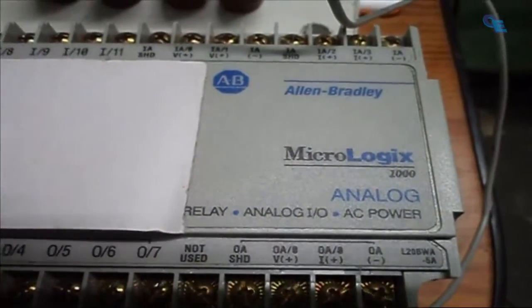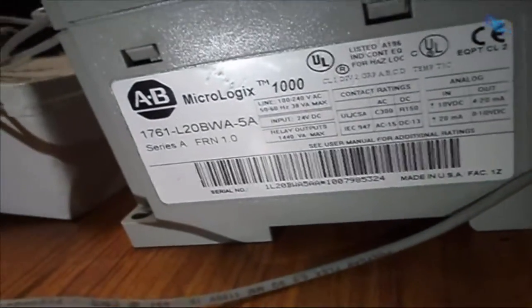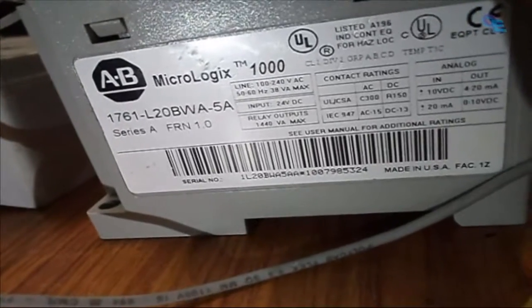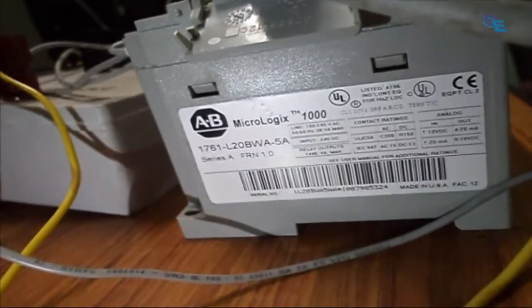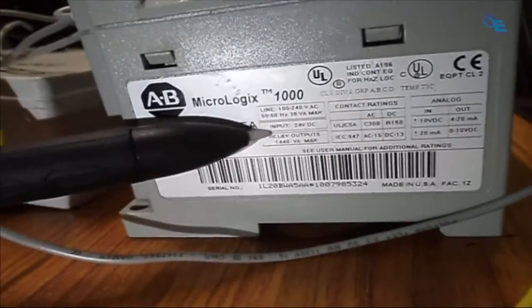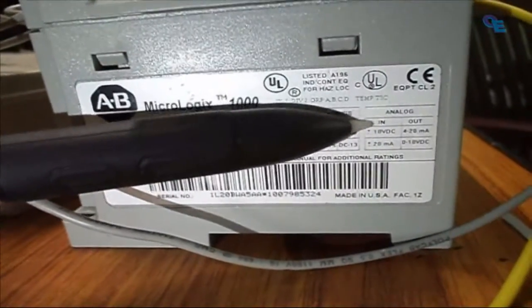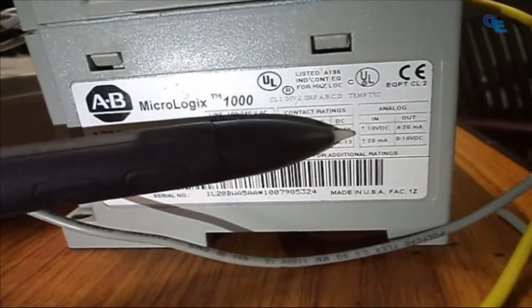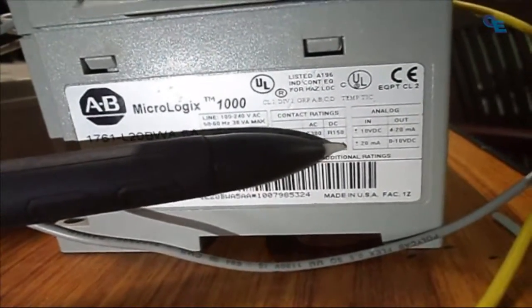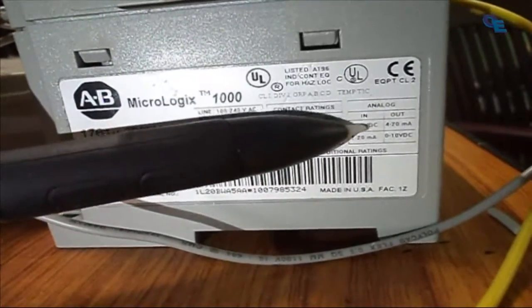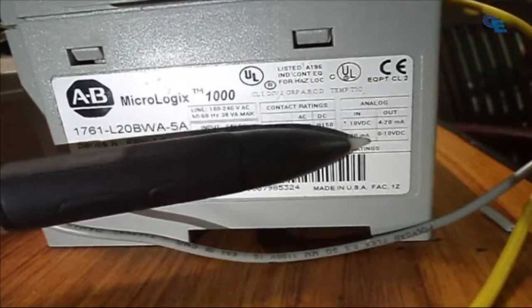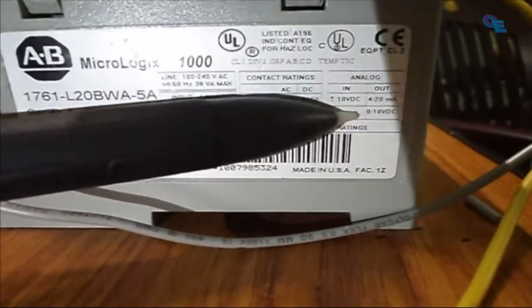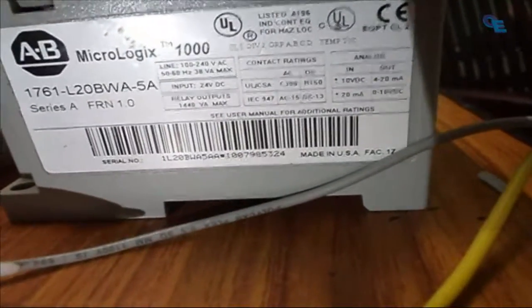Using analog PLC, that is MicroLogix 1000 analog PLC, we can check the input and output ratings here also. Here we can check the input is of 24 DC and output is of relay type. At the analog side, the input is plus or minus 10 volt DC or plus or minus 20 milliamps, and at the analog output side we get 4 to 20 milliamps current, or in voltage type 0 to 10 volt.